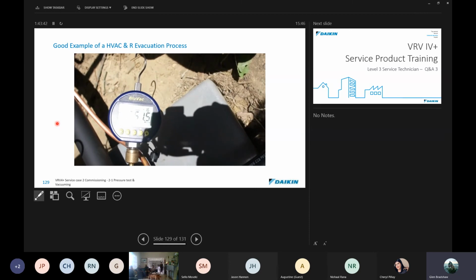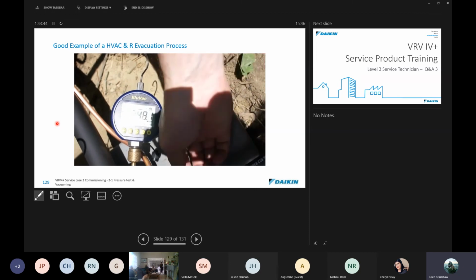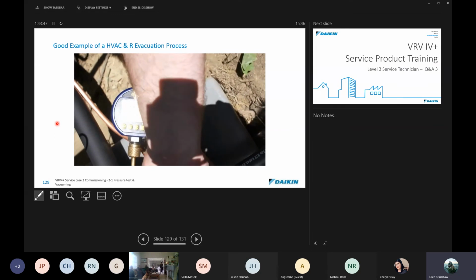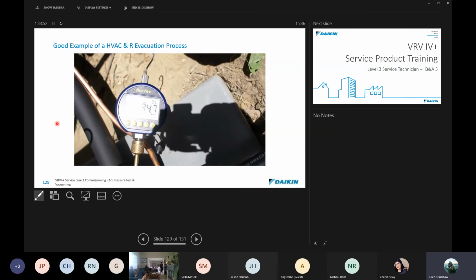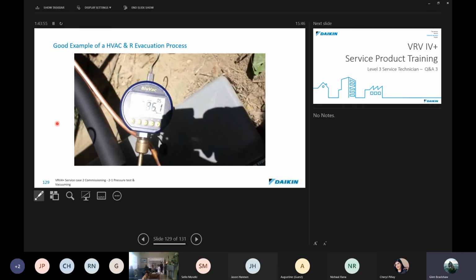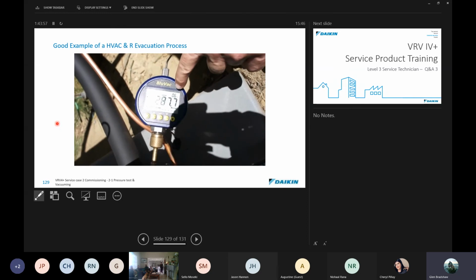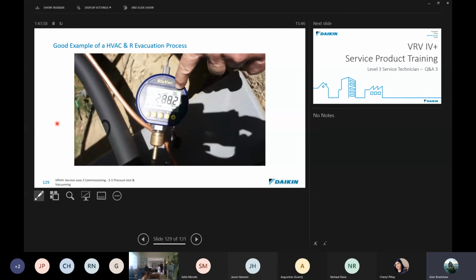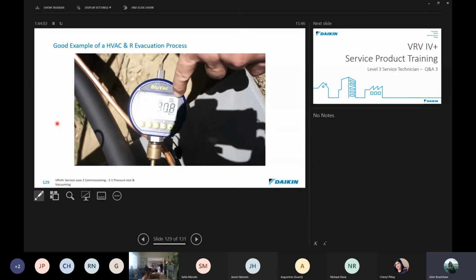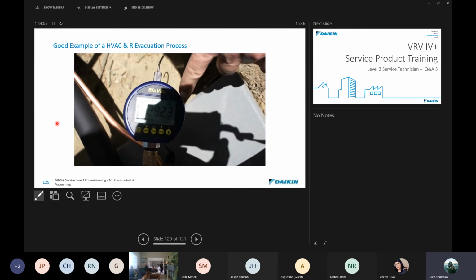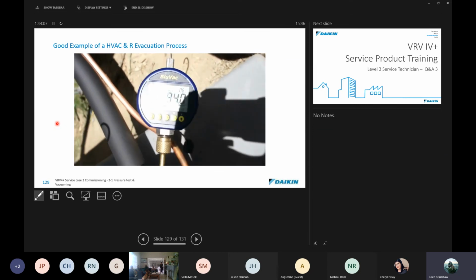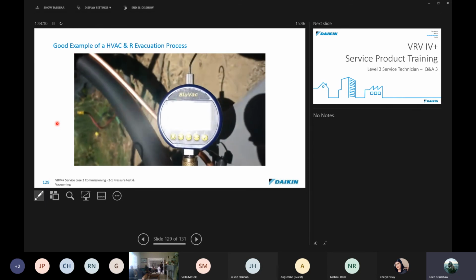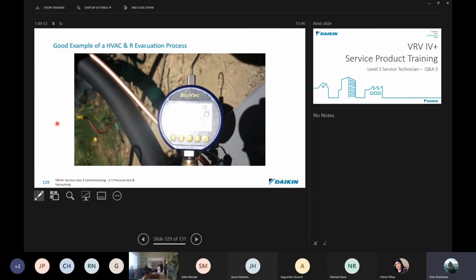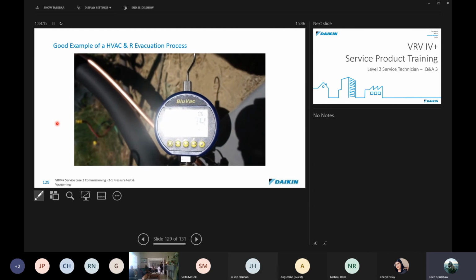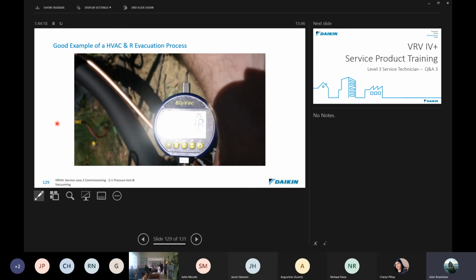The important thing now is that we do a standing pressure test and let this sit for a minute, make sure that we're not having any problems with outgassing. I'm going to valve off my 2 core tools, and we're going to let that stabilize. So now there's no vacuum pump on this. You can see right here, here's our leak rate. We're at 0.6 microns per second of rise right now. We're holding right there at 296, 297. We're going to let this run a little bit longer, and we'll just pull this down just for good practice.